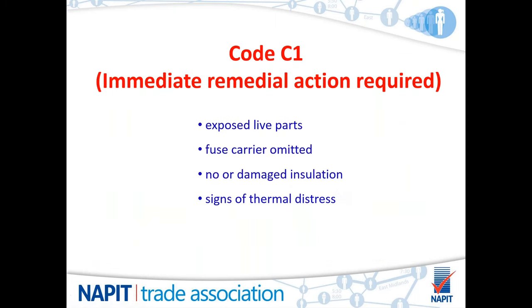For C1s, reading the regs, immediate remedial action required. Basically speaking, it means death the minute you touch it. Anything that would cause a danger to life at that time should be recorded as a code C1. Some examples are obviously exposed live parts, any fuse carriers omitted from distribution boards, consumer units, any damaged insulation to cables leaving the conductors exposed, and any signs of thermal distress caused by loose connections that obviously could lead to fires and the likes.